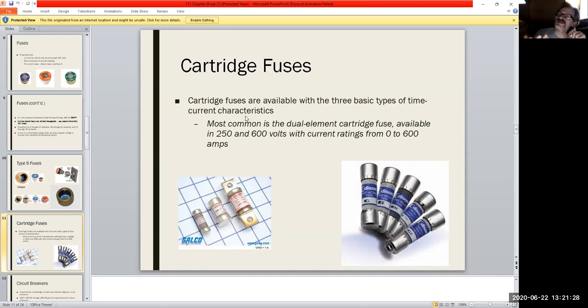Now, it's when the device doesn't settle down that we have a problem, like the device is malfunctioning in some way, drawing too much current, and now it's going to become a danger. The way these fuses are set up is by a time delay. You don't want the time delay to be so short that it's always going to trip every time something powers up, because it's always going to have that instantaneous rate of charge and then settle down. So you want to give it that time. And then, of course, if it hasn't settled down within the allotted amount of time, then for protection, you want your circuit breaker to trip, protecting you and protecting the device from bursting into flames or exploding or God knows what. These types are all set up for different time bases, and it depends on the device.